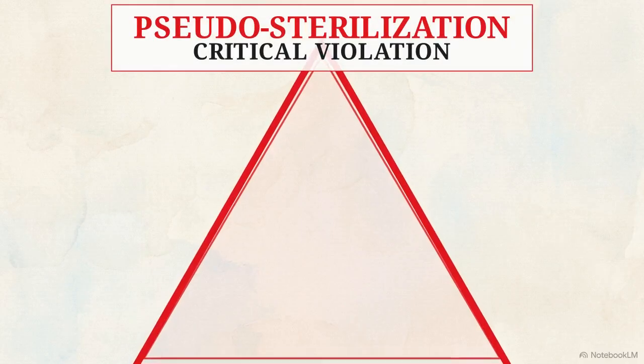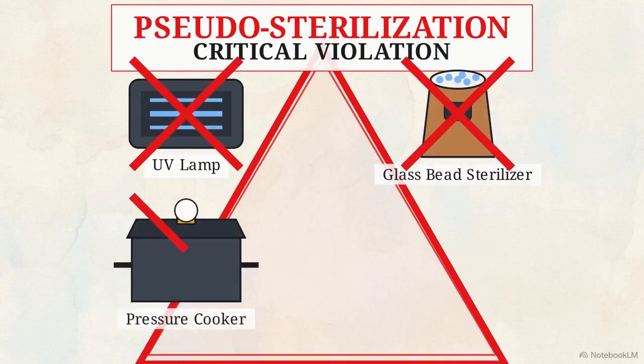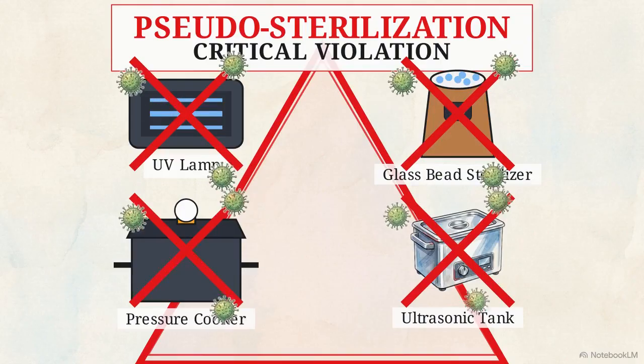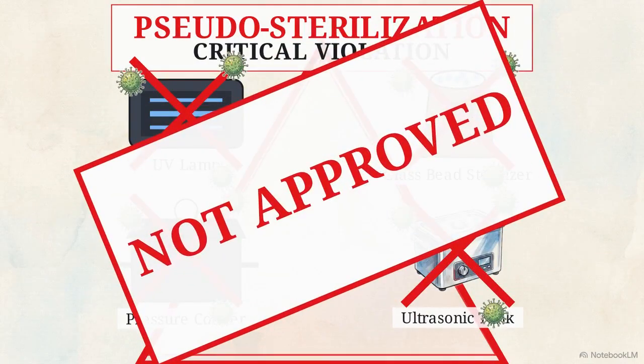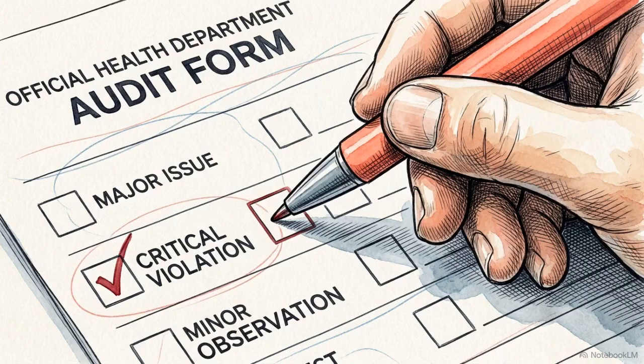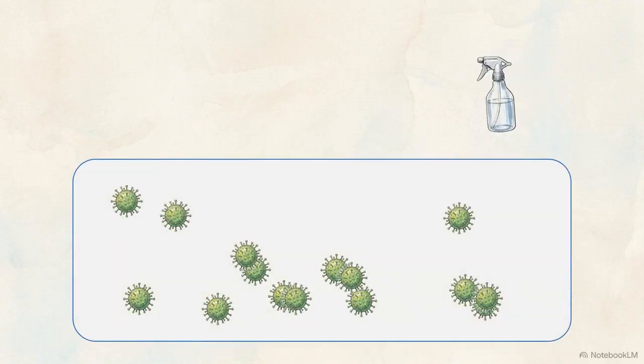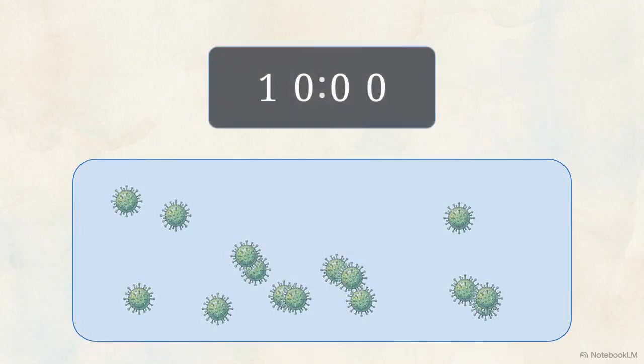This graphic highlights the methods inspectors actively target for violations. UV lamps, glass bead sterilizers, pressure cookers, and ultrasonic tanks cannot assure sterile conditions and are not legally approved sterilization methods. Using one of these unapproved methods, or misclassifying a critical tool into a lower disinfection tier, instantly triggers a critical compliance violation. This timer illustrates the most frequent execution failure in any shop.